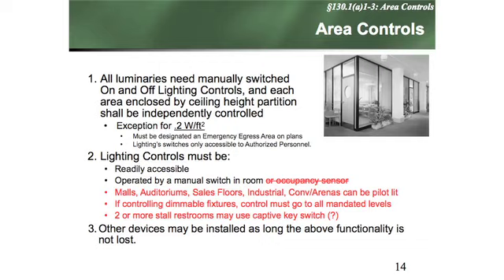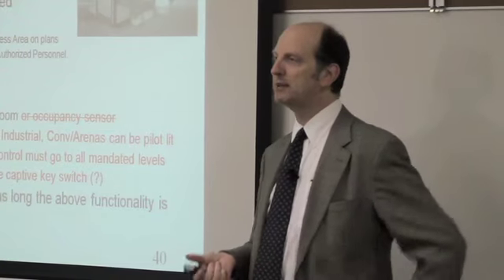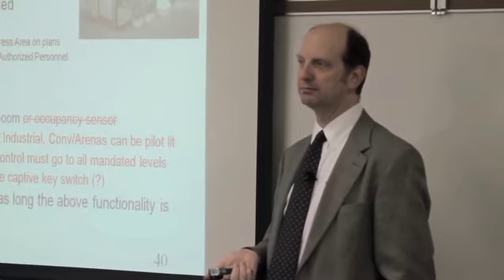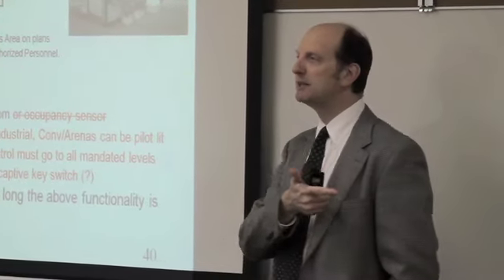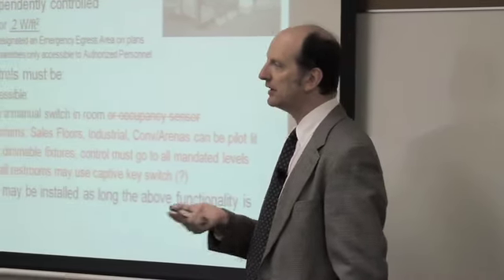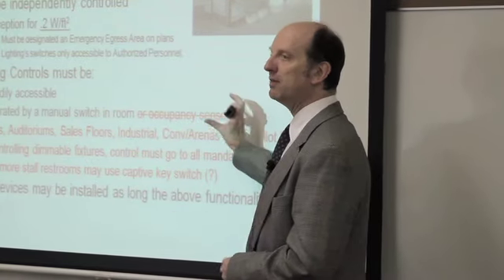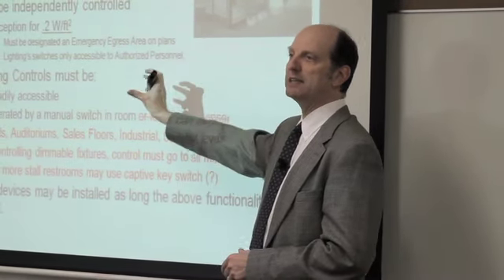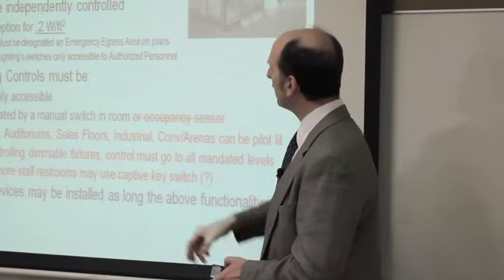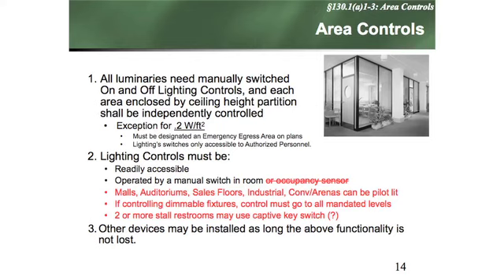Area control is simple: in any given space, somebody should always be able to turn off their lights. How many times have you been in a space without a switch on the wall? Not often—but it's important enough that they made sure every space has one. The code requirement, in black, is the same as before: make sure there's a switch device so people can always turn the lights on and off. You can add whatever automatic controls you want, but people must always be able to go to a lower or off level if they choose.